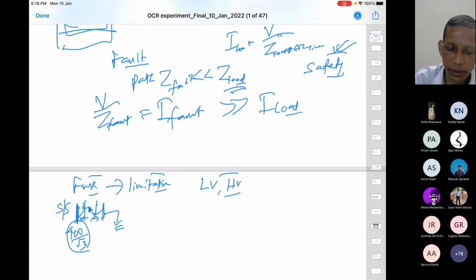But because of the corresponding inductance of the system and half Li square and all these things, and with higher and higher voltage, the gap requirement becomes maybe in terms of meters. The gap requirement becomes in terms of meters, and 400 kV, 765 kV, 800 kV, 1000 kV systems are in operation today. So therefore, the fuse finds a limitation that it is not reliable.